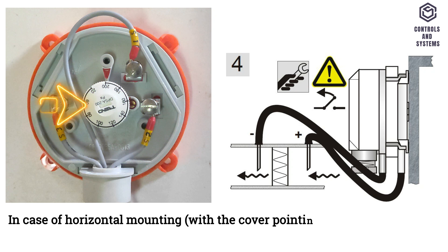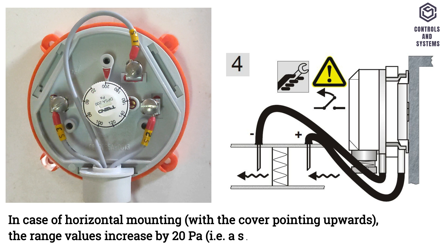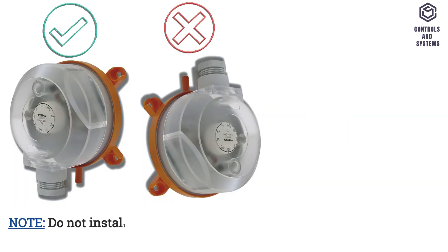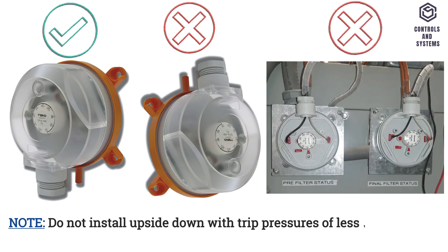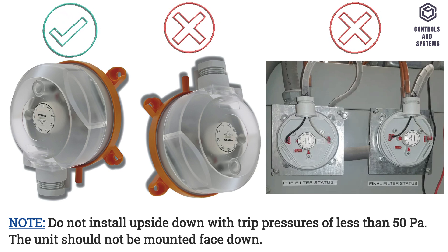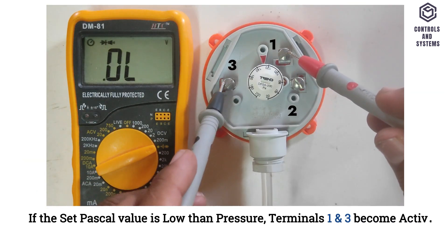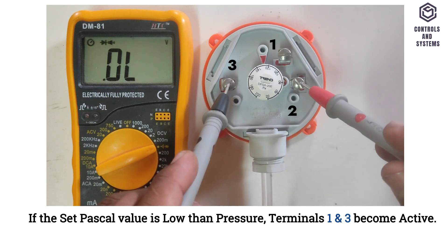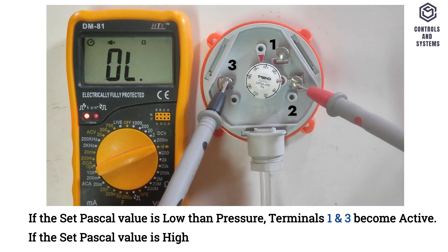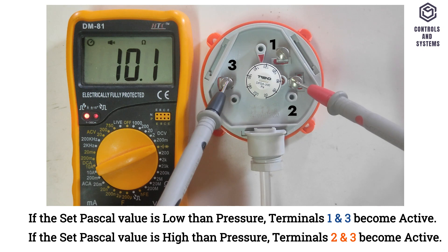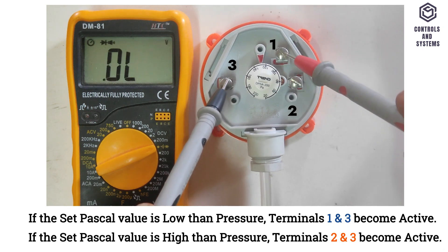In case of horizontal mounting with the cover pointing upwards, the range values increase by 20 Pascals — for example, a setting of 40 Pascals will switch at 60 Pascals. Do not install upside down with trip pressures of less than 50 Pascals; the unit should not be mounted face down. If the set Pascal value is lower than the pressure, terminals 1 and 3 become active. If the set Pascal value is higher than the pressure, terminals 2 and 3 become active.